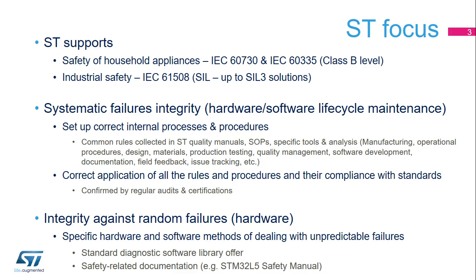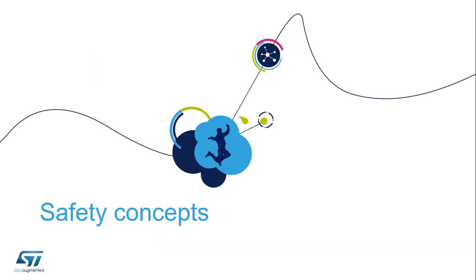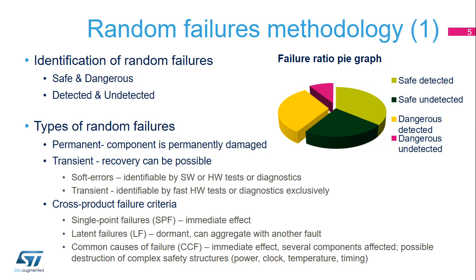To ensure integrity against random failures, specific software methods and hardware design techniques must be applied as described in the following slides. Not all random failures result in a hazardous event, and they may even be considered as safe from a safety point of view. Safety standards require monitoring to detect dangerous failures that may be directly or indirectly related to safety and have the potential to cause a dangerous situation.